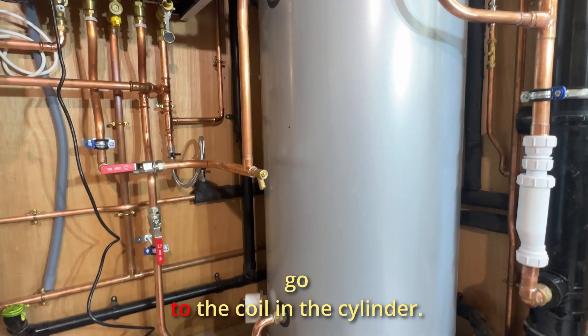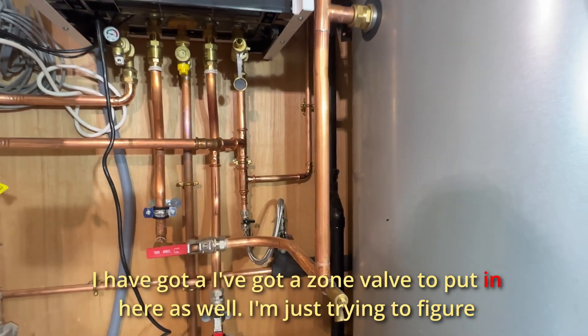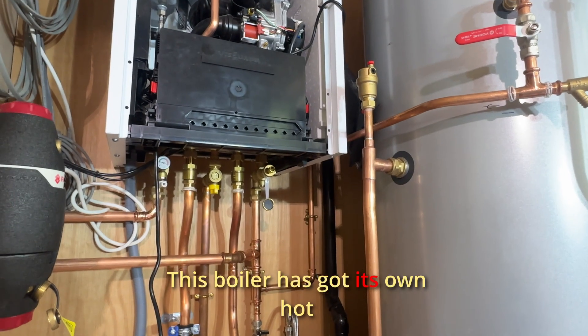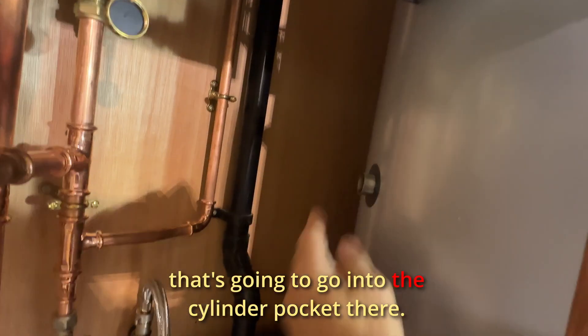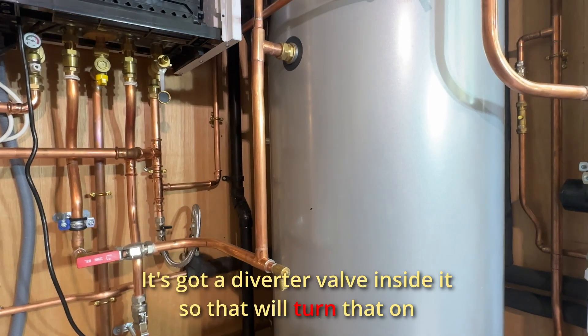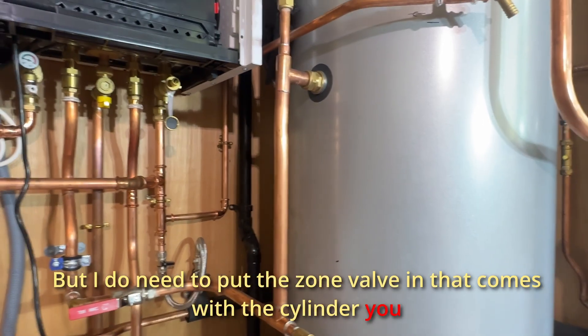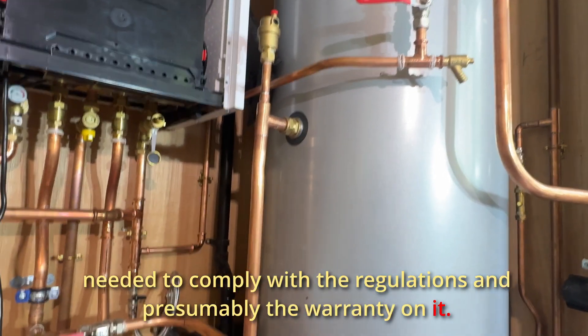There's another flow and return that goes to the coil in the cylinder. I've got a zone valve to put in here as well — I'm just trying to figure out the most sensible way of connecting it. At the moment this boiler has got its own hot water thermostat that's going to go into the cylinder pocket there. It's got a diverter valve inside it, so that will turn that on and off as needed when the water gets to temperature. But I do need to put the zone valve in that comes with the cylinder, as it's needed to comply with the regulations and presumably the warranty on it.